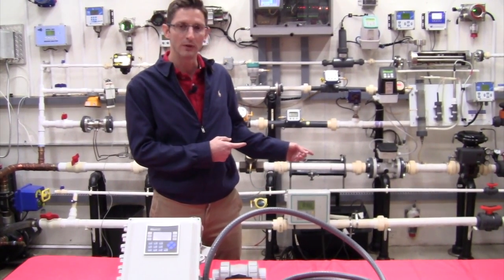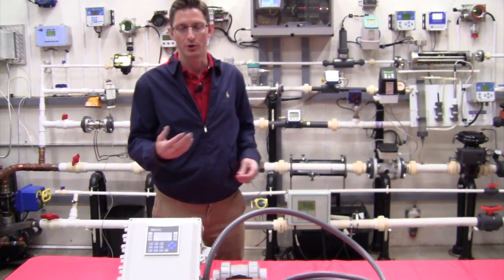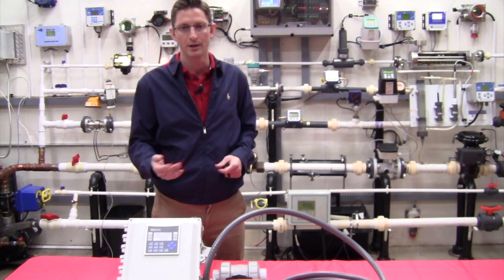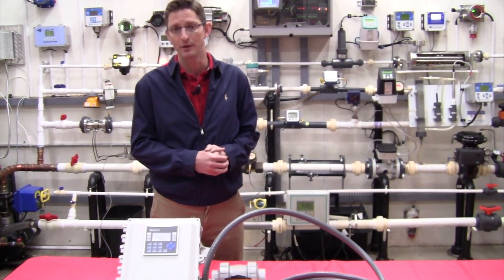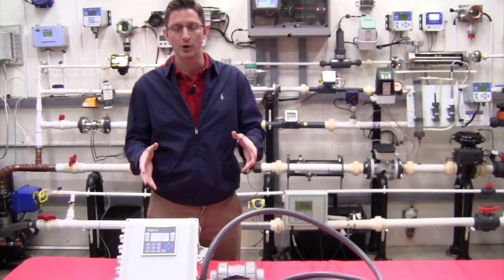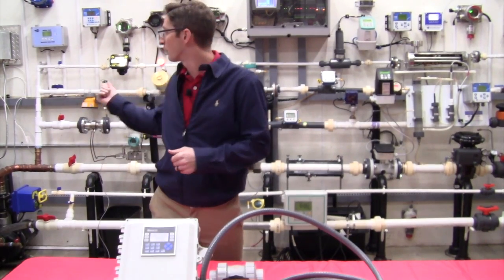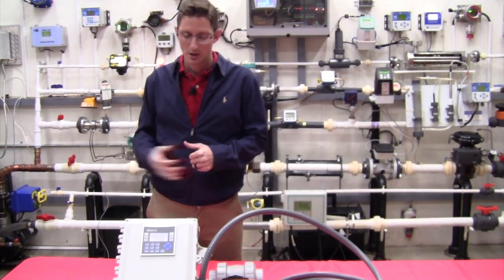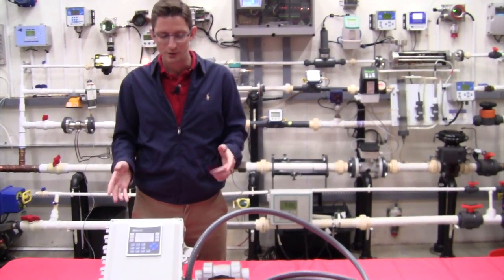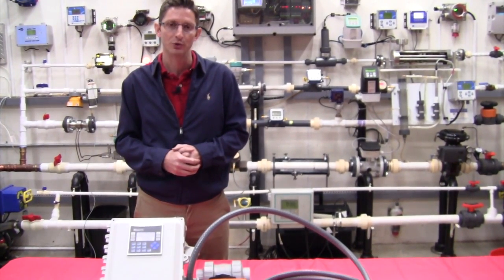The calibration that we've just done is on water. You're going to be doing bleach or sodium hypochlorite, which has a slightly different specific gravity. So you always need to do the calibration on whatever process you are flowing through your meter. That's it for a calibration. The next step will be showing you how to troubleshoot these flow meters.